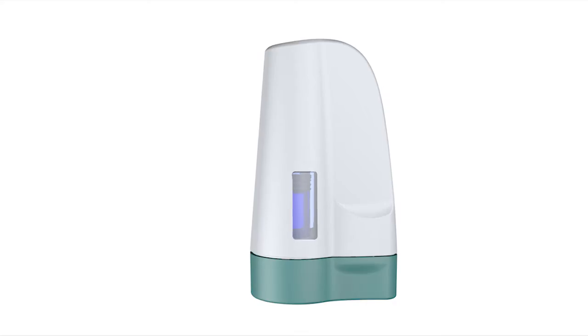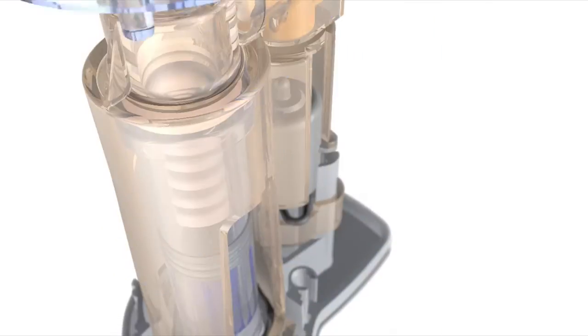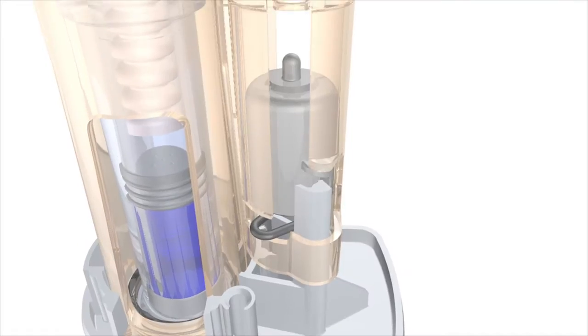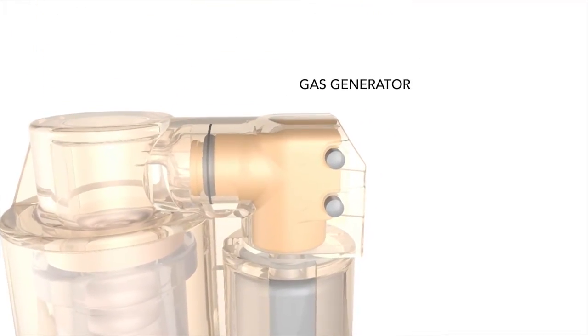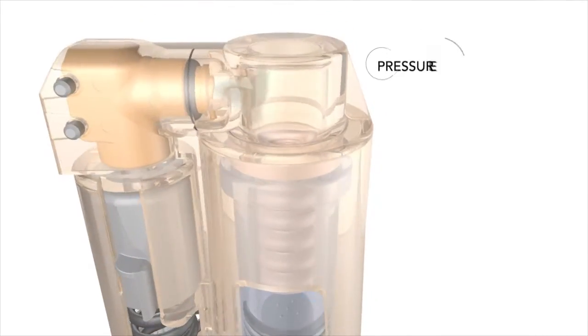Crossject's needle-free auto-injector utilizes a totally unique, energetic, materials-based gas generator, miniaturized from airbags and pre-tensioning seat belt systems used for automotive safety. The gas generator produces gas just at the moment of the injection and the liquid drug is expelled at high speed from Zeneo.